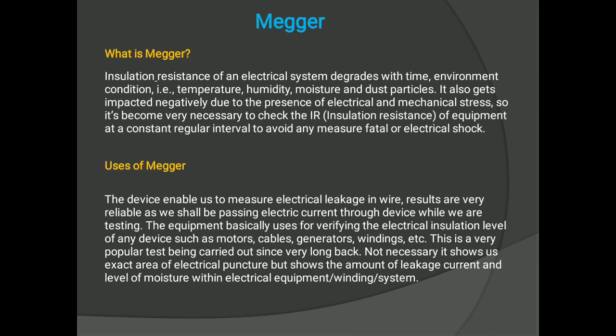Now we will study the Megger, the working principle of the Megger, which is used for measurement of high resistance or insulation resistance. What is a Megger? The Megger is an instrument which is used for measuring high resistances of the order of mega ohms and for testing insulation resistances. The instrument generates its EMF when the cranking handle is turned.